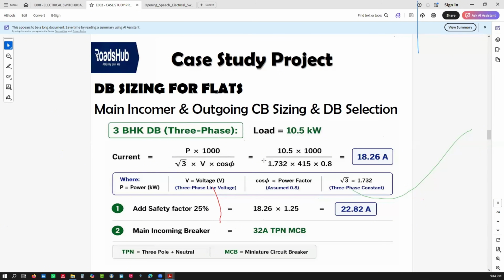The same math, the difference is you have a root 3 here. So you do the math, and then just remember, your power is in kilowatt, and your 3-phase voltage is 415. That's the difference now, because the other one was single phase. And then assumed power factor will be 0.8, and then the three-phase constant needs to be included. But the safety margin still sticks. So you need a 1.25 extra.